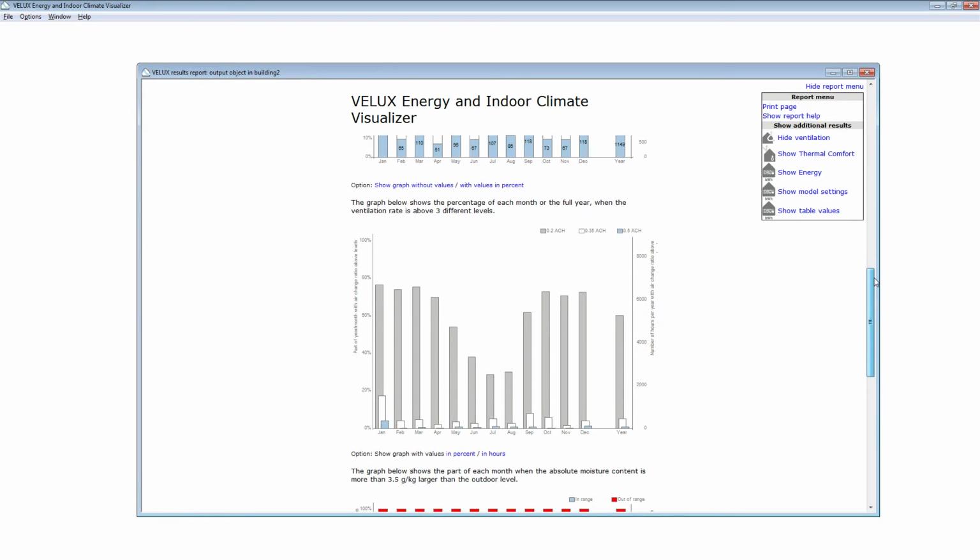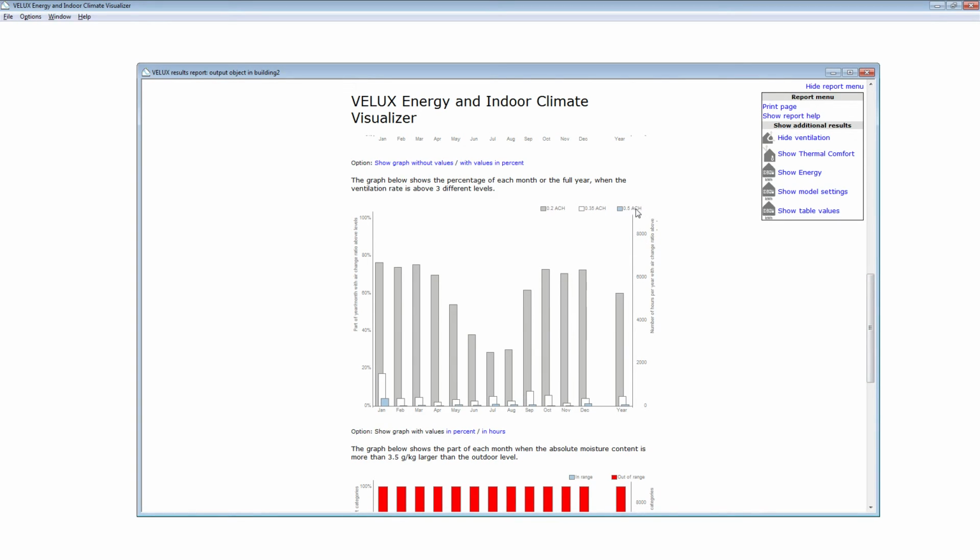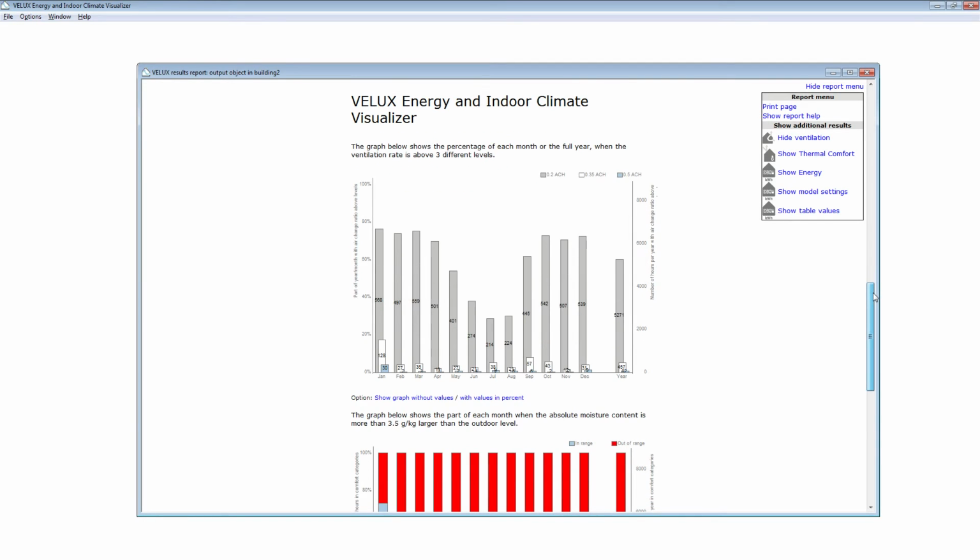Also, we can look at the air change. This is 8 air changes per hour, and then we can actually go in and see, okay, we have a very limited air change in the summertime, and during the whole year we have an average here of, that's not actually possible to see, but we have to go into the tabular data to actually see the average of this year.